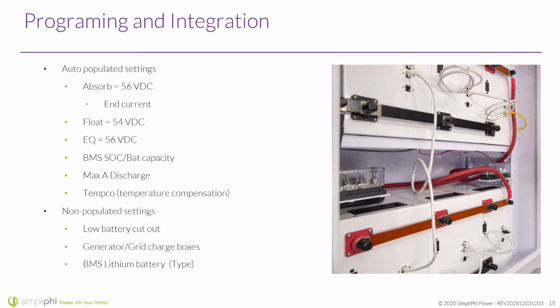The end amps or end current, that'll auto-populate. Settings like float, if it's being used. EQ auto-populate, though it's not going to be used, and the system will automatically know that. The state of charge, the battery capacity will be automatically populated to the inverter. The max discharge and the max charge, and the temperature compensation. Those are all auto-populated set points. And then we go to non-auto-populated set points.